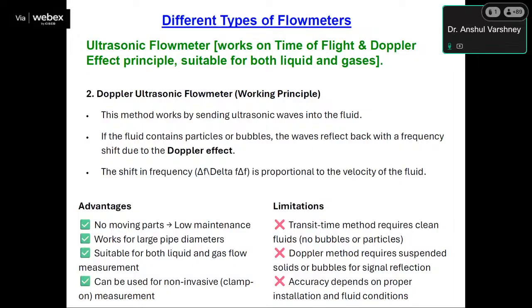The advantages of ultrasonic flow meters are that there are no moving parts, similar to the electromagnetic flow meter. It works for large pipe diameters, is suitable for both liquid and gas flow measurement, and can be used for non-invasive measurement. Non-invasive measurement means that if you are using ultrasonic flow meters, there is no need to open or dismantle the pipeline. You can mount the transducers on the outside of the pipe.